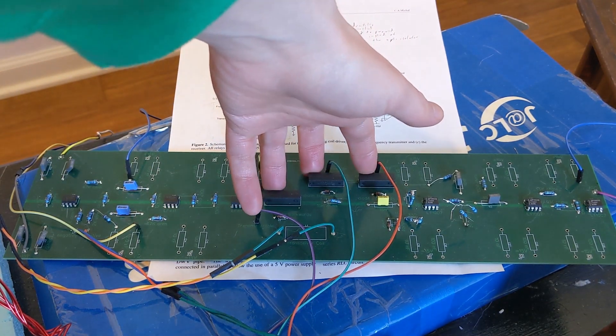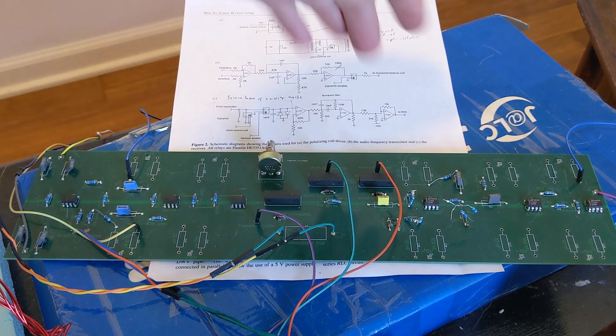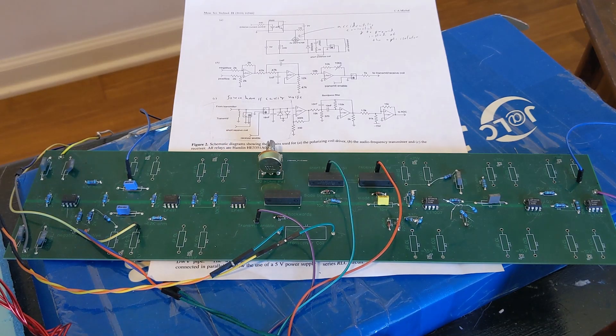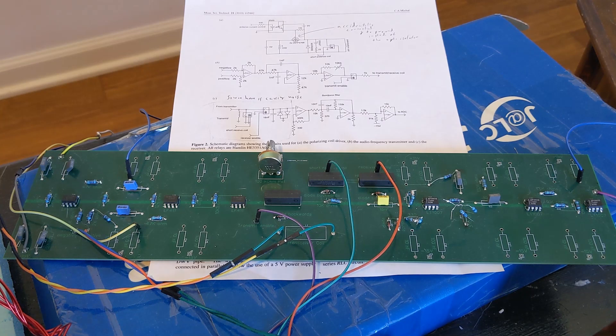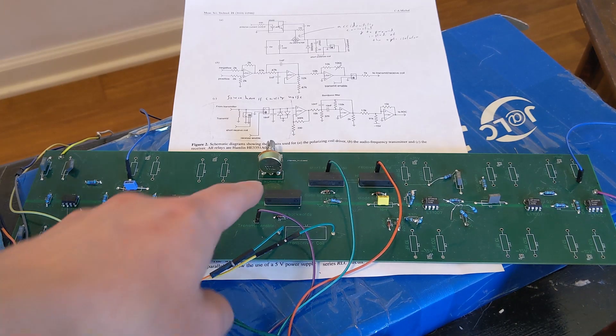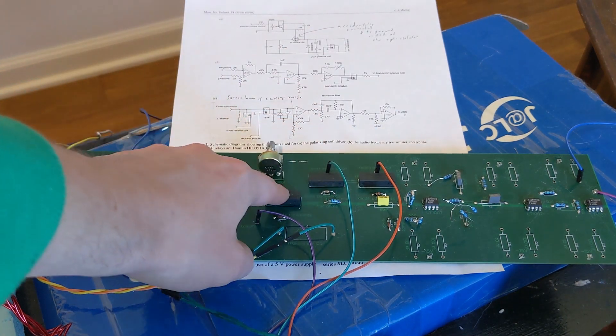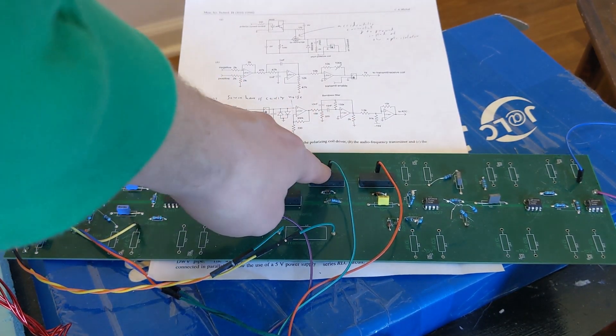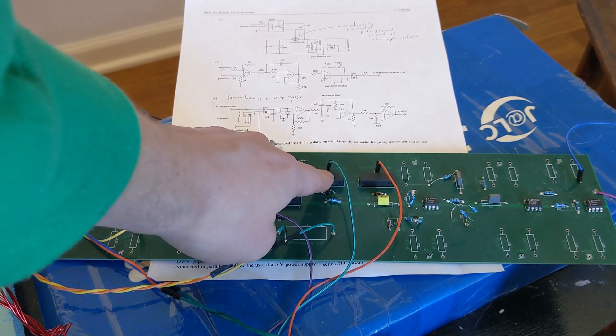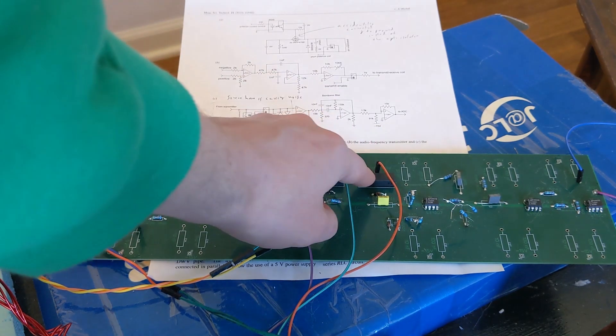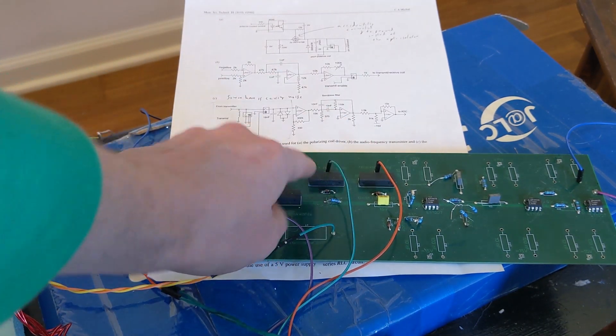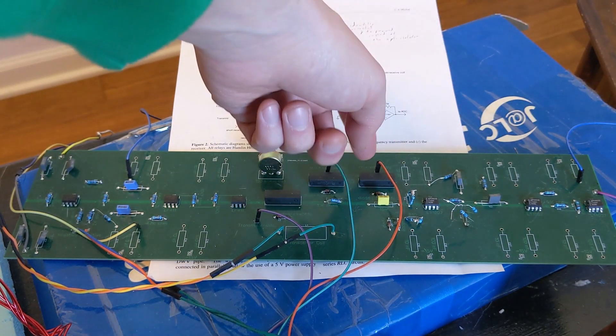These three relays right here kind of help us time everything. So it lets us connect the transceiver coil to ground so everything's quiet. There's no background noise that gets built up into there. Then as soon as we're ready, we cut that so we unground the coil. Then we open up the transmitter so that we can send information into the coil. And then we open up the receiver and then we close the listener so that any noise back here can't get to the front of the system. And we listen to the response from the hydrogen nuclei.